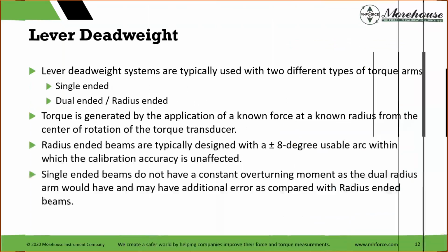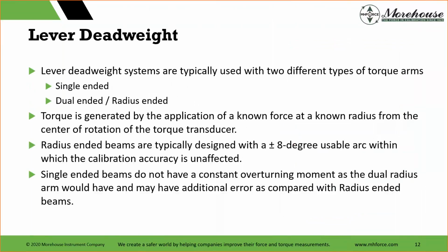And then if we start going over, lever systems are typically used for two different types of torque arms, single-ended and dual radius. Torque is generally generated by the application of a known force at a known radius from the center of rotation of the torque transducer. And when manufacturers design the radius beams, they are typically designed with a plus or minus 8-degree usable arc, within which the calibration accuracy is unaffected, because that arm's going to bend, right? It's going to bend, and you have the arc to make sure your distance and everything is the same.